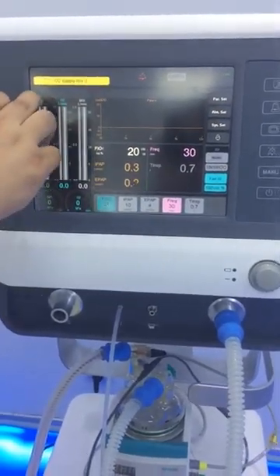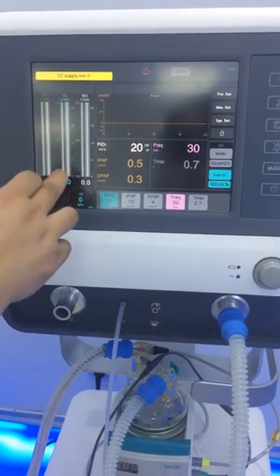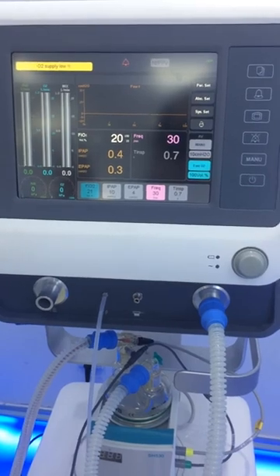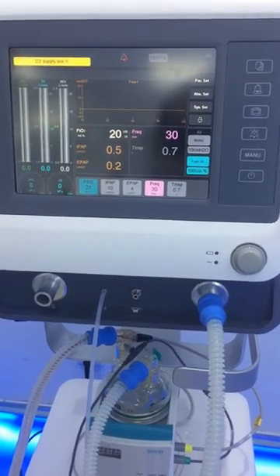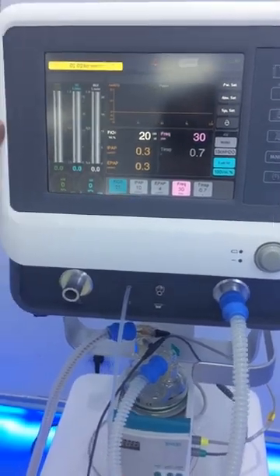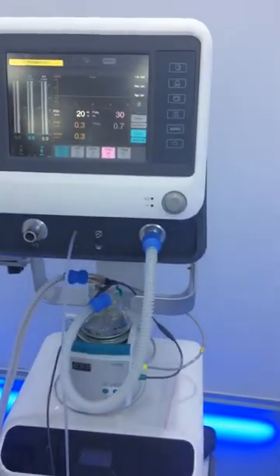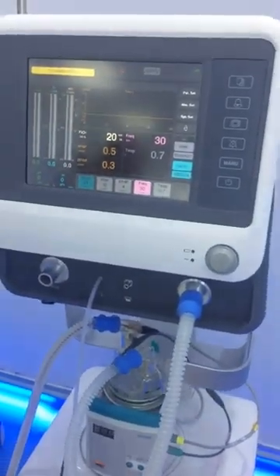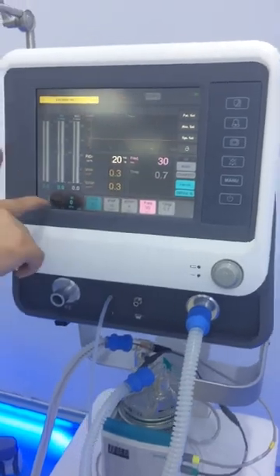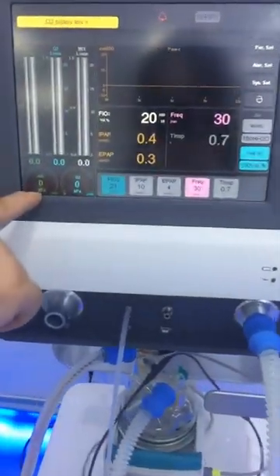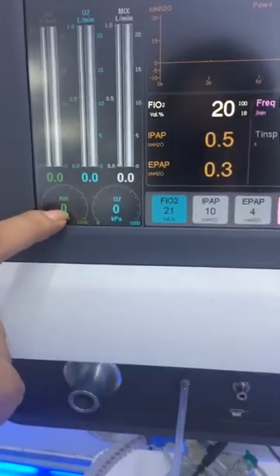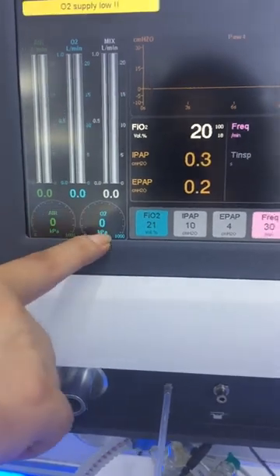So here the first flow will be the air, the second will be the oxygen, and the third one will be the mixed. That means if the air is 3 and oxygen is 5, then the mix will be 8. So it's very accurate for doctors to check the parameters. And also here we are not using the pressure gauge anymore, but we are using the digital display shown on the screen.